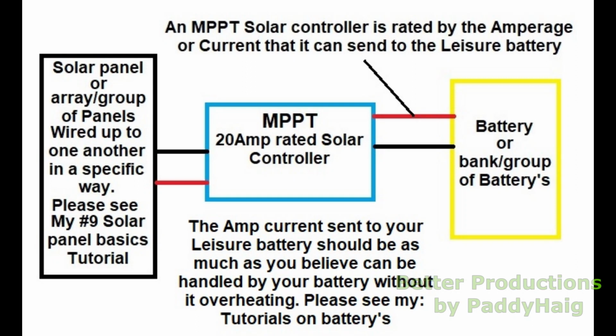My MPPT controller is actually rated at 20 amps. However, via the software, which you log into via your phone, I've reduced that 20 amps down to 18 amps. As I mentioned earlier, you could have a 30 amp MPPT solar controller, and on some models that allow software changes, there are even hardware changes, where you can just move a pin. On mine, I was able to reduce it from 20 amps down to 18 amps maximum.